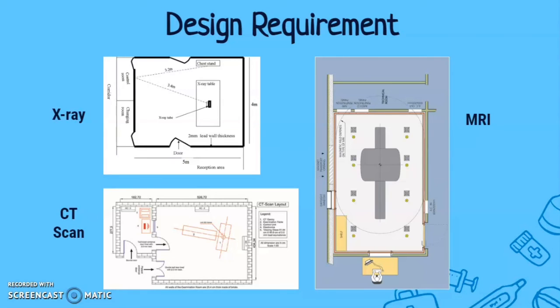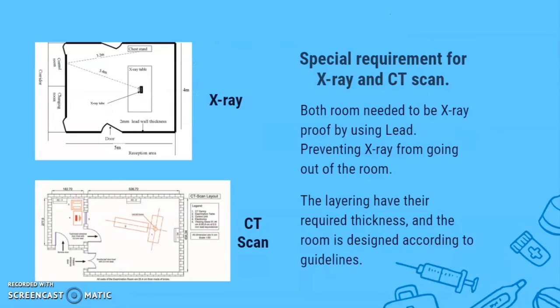Hi, this is Syamil again, and I will be presenting the design requirements for the imaging modalities room. The design requirement of the imaging modalities room differs from one another. For X-ray and CT scan room, both have the same requirements for the room design and material usage for the barrier. Both rooms need to be X-ray insulated.